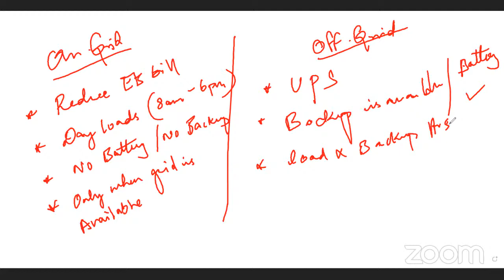It doesn't restrict that you have to be a day load user or a night load user, but you need to mention what is the load and what is the backup hours. This is very, very important, because I need my 500 watts of load to be operated for 5 hours — that is your actual requirement. You have to arrive at what is the total load and for how many hours it has to be operated. That should be arrived at properly before designing or choosing an off-grid system.